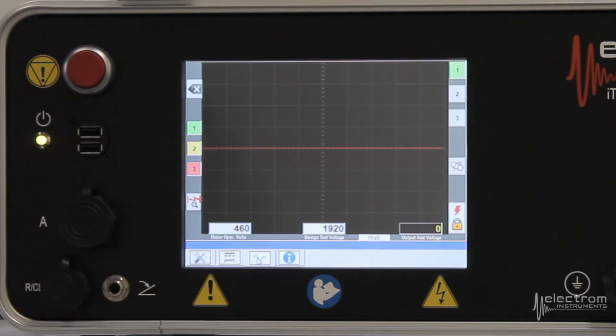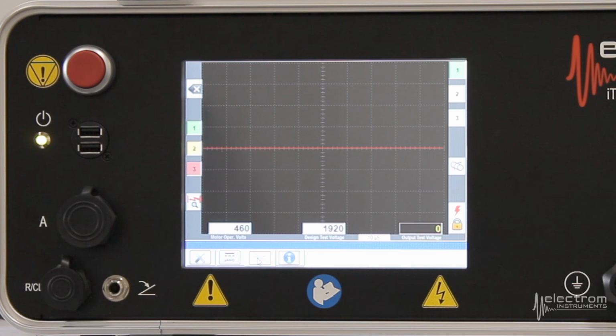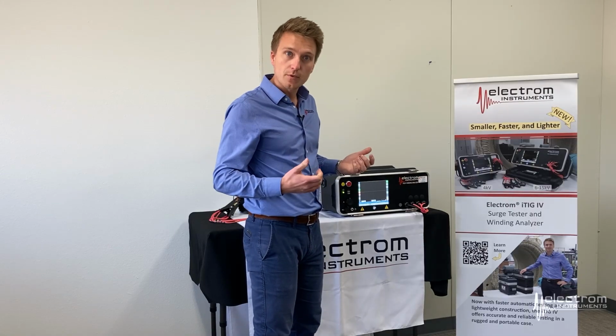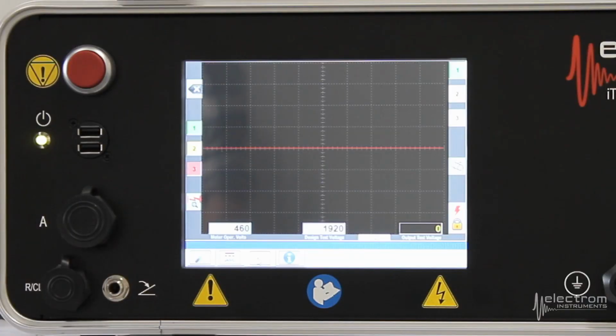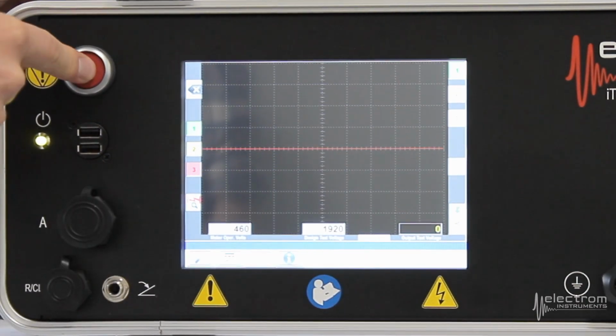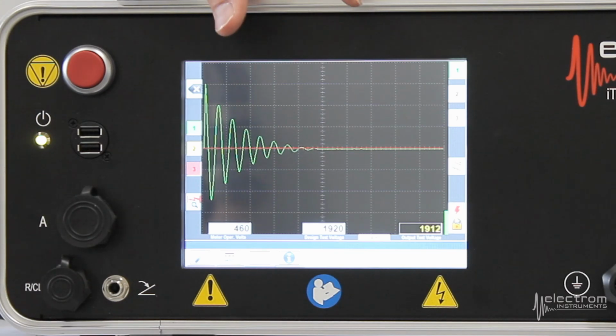Next tab over, surge screen. Number 1 is highlighted in the top right corner. That means that phase 1 or lead number 1 will be energized first. We have told it what voltage to go to, in this case 1920 volts. You arm the instrument, hit the red button, and the instrument will automatically set the time base and voltage scale and then drive the voltage to 1920.